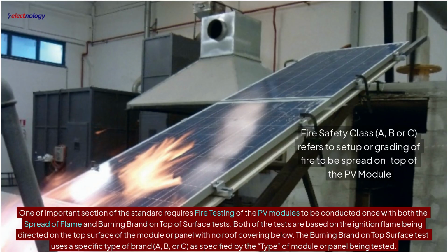One important section of the standard requires fire testing of the PV modules to be conducted once with both the spread of flame and burning brand on top of surface tests. Both of the tests are based on the ignition flame being directed on the top surface of the module or panel with no roof covering below. The burning brand on top surface test uses a specific type of brand, A, B, or C, as specified by the type of module or panel being tested.